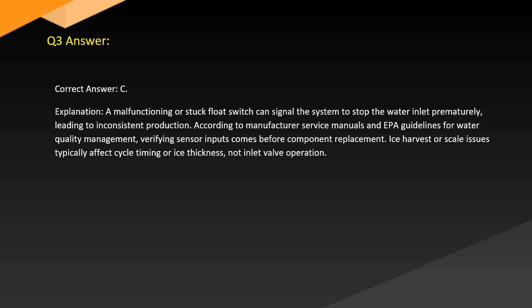Answer. Correct answer C. Explanation. A malfunctioning or stuck float switch can signal the system to stop the water inlet prematurely, leading to inconsistent production. According to manufacturer service manuals and EPA guidelines for water quality management, verifying sensor inputs comes before component replacement. Ice harvest or scale issues typically affect cycle timing or ice thickness, not inlet valve operation.